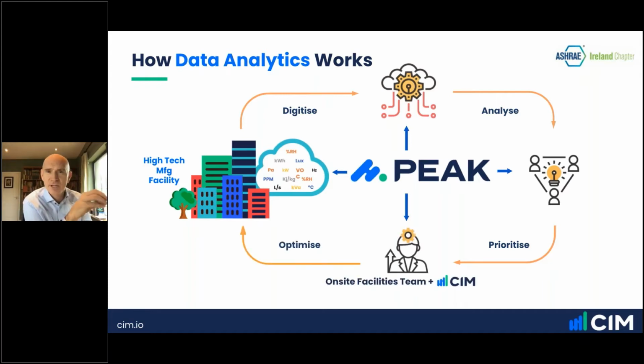And the last piece here is kind of where the rubber meets the road. It's bridging the gap between the identified savings and what the site can actually realize. And how we solve that at our site is our engineers collaborate and engage directly with the technicians that are on the coalface on the site to resolve what the software is identifying as an issue. And that optimization then happens on the site.